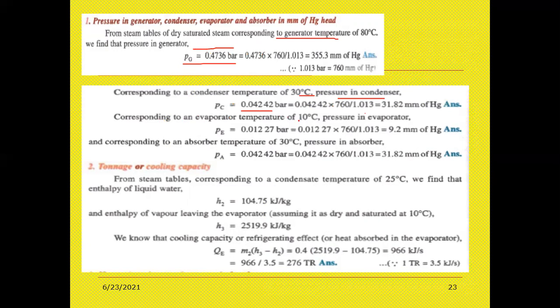Now corresponding to the evaporator temperature at 10 degrees centigrade, Pe is equal to 0.01227 bar into 760 divided by 1.013, that is equal to 9.22 mm of Hg. Now corresponding to an absorber temperature of 30 degrees, the pressure in the absorber, Pa, is equal to 0.04242 bar, is equal to 0.04242 into 760 divided by 1.013, that is equal to 31.82.